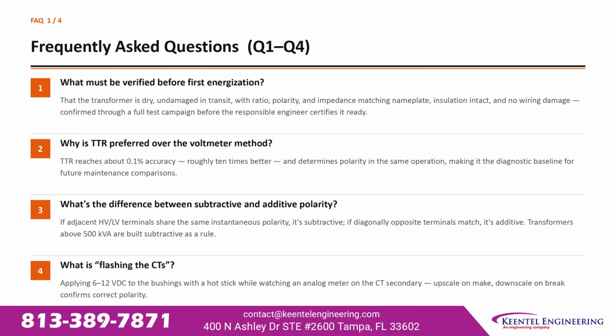Why is TTR preferred over the voltmeter method? TTR reaches about 0.1% accuracy, roughly 10 times better, and determines polarity in the same operation, making it the diagnostic baseline for future maintenance comparisons.